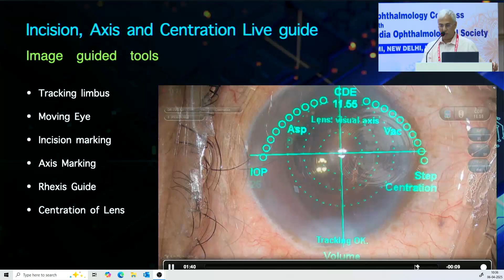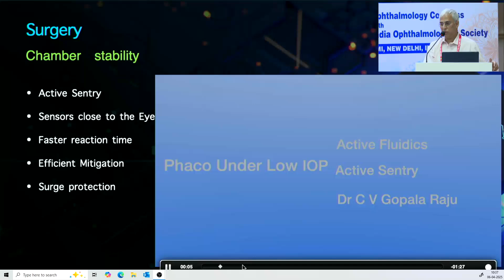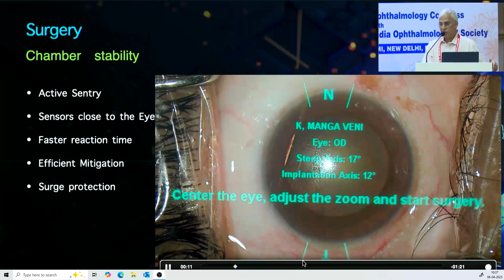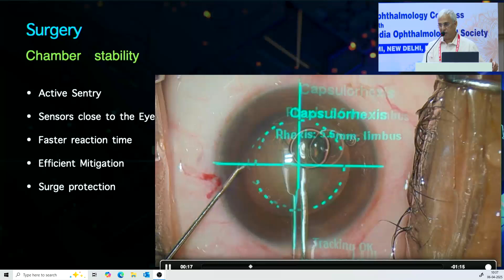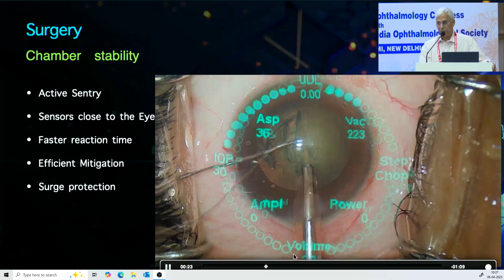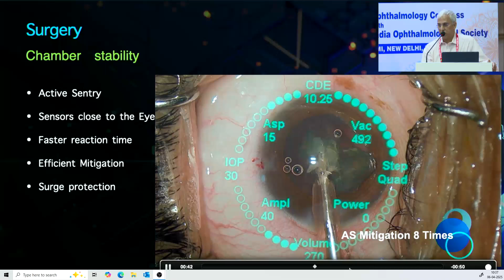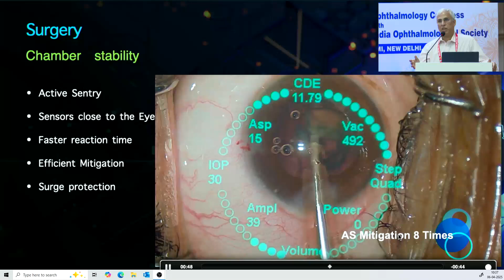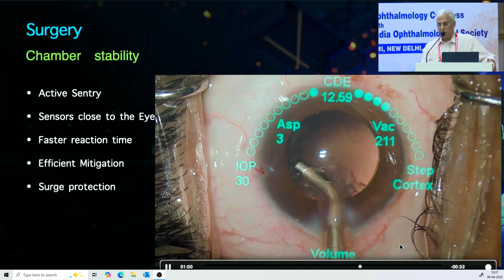Then comes the chamber stability. When it comes to the surgical aspects, the Centurion machine now has Active Sentry fluidics, where the sensors are placed right in the phaco probe, very near the chamber, in fact in the chamber. So even in the shortest time, they capture the fluctuation in the chamber, and the corrective measure is done immediately. If you can see here, 8 times the probe has detected and corrected itself and prevented it from happening. This is the kind of sensor they have developed. With that input and the software design, they can go to mitigation and prevention.